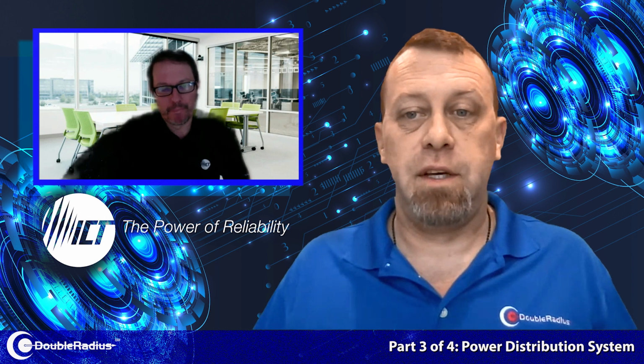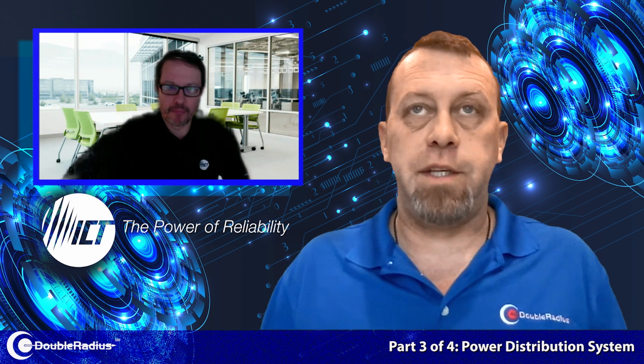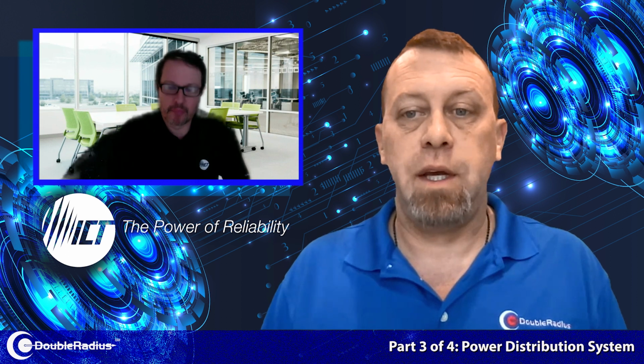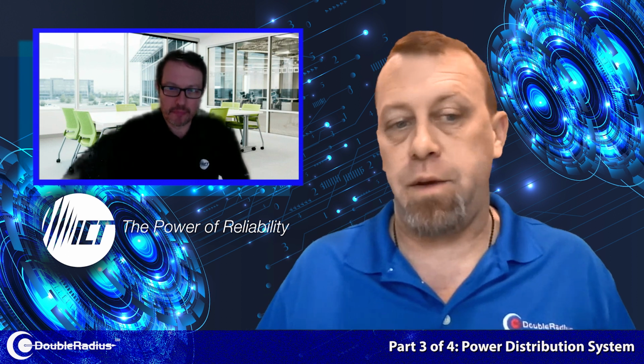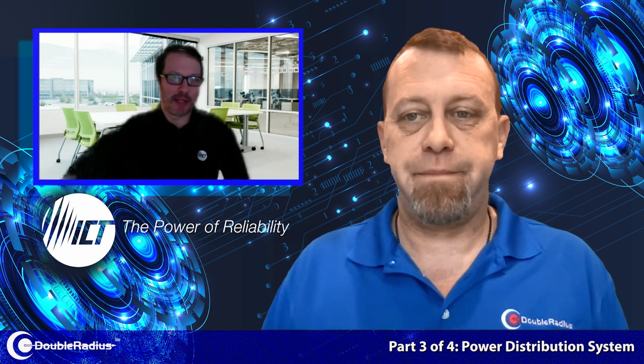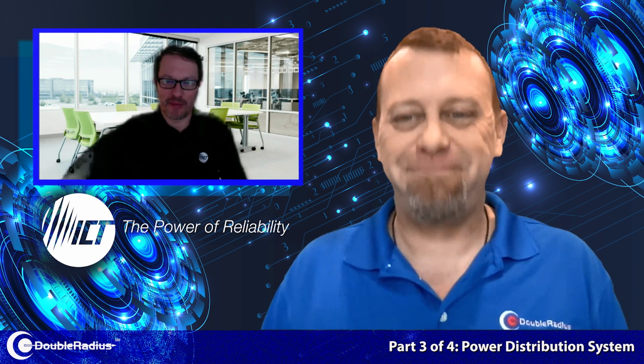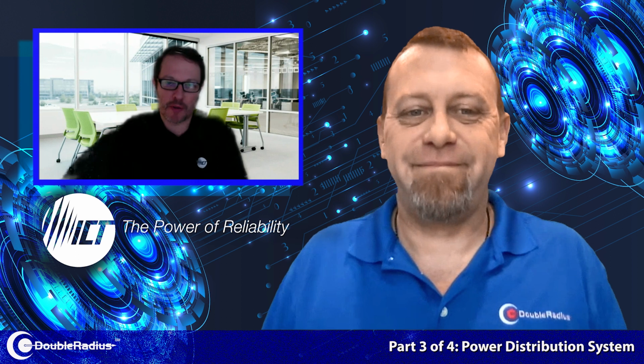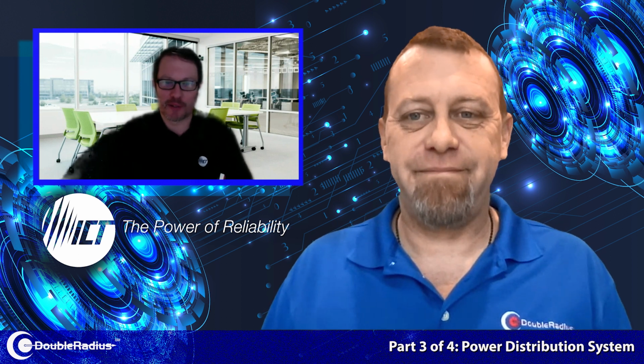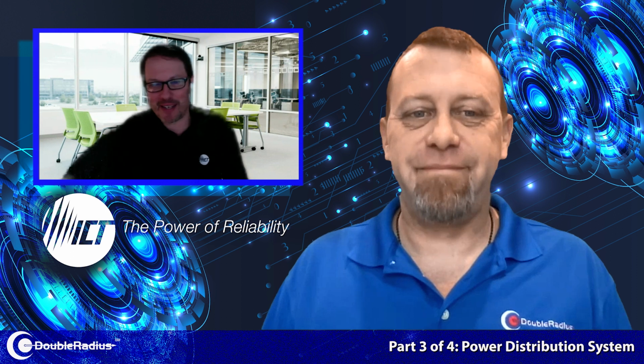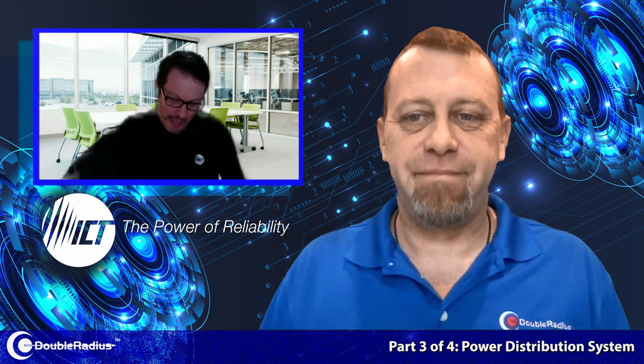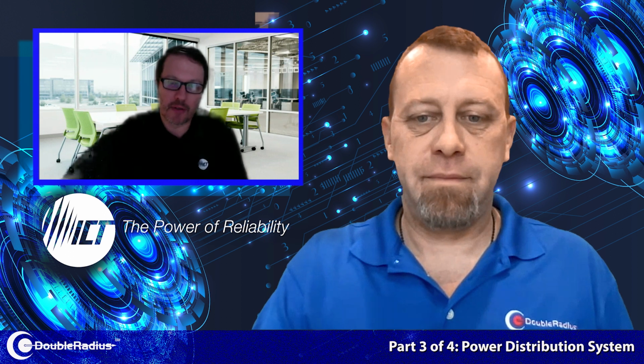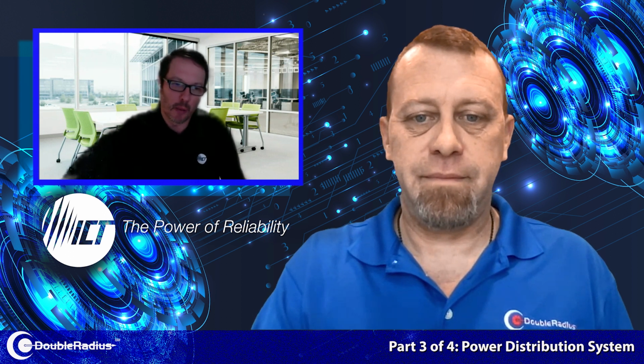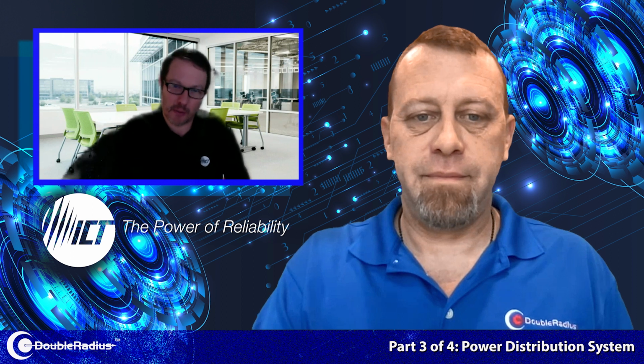That's cool. And to go back to what you said earlier with the intelligence, so being able to control each bus or each breaker or everything else, that gives you the ability to remote power cycle your radios, correct? It does. So you could look at a DC distribution panel similarly to a network switch, where you've got all the traffic and you've got individual devices connected to it, and they're managing the network traffic. A DC distribution panel is almost like the switch, but it's a DC type device, and it distributes the DC. So yeah, in each of the individual outputs on the intelligent versions of ICT's distribution panel, we actually have a relay that you can use to disconnect your load devices.